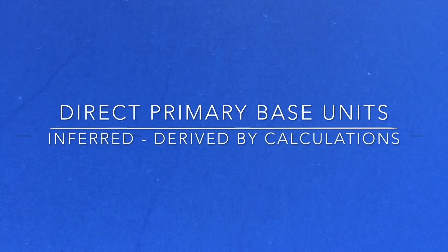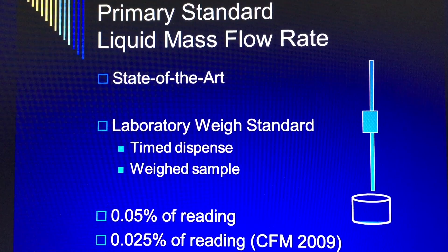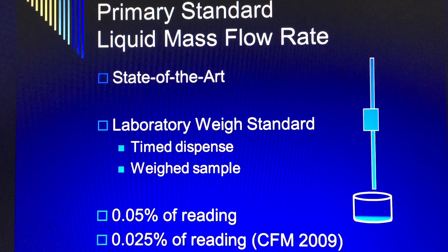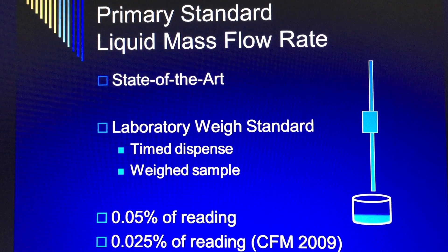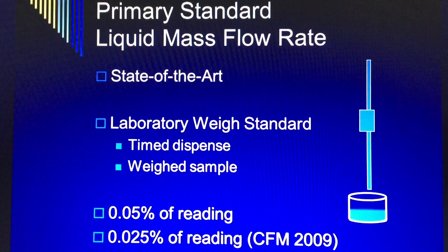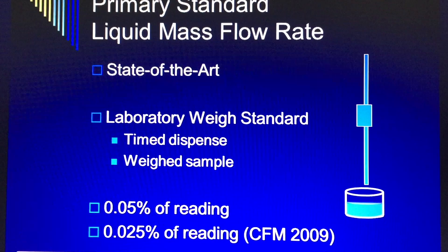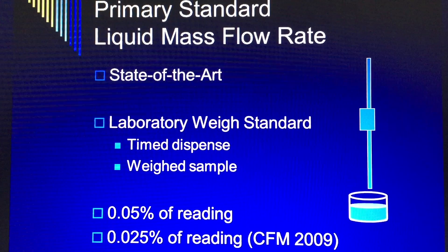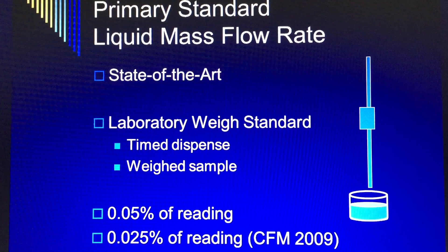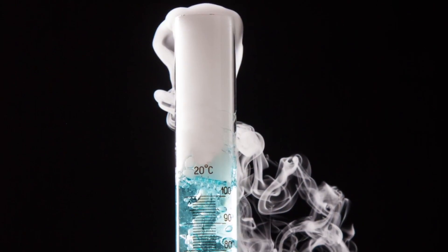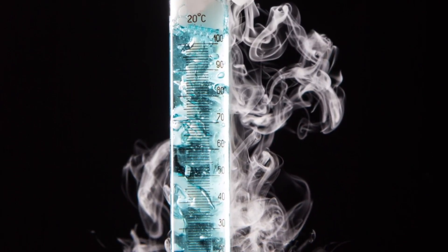Flow rate can be measured directly using primary base units or inferred, derived by calculations. A timed dispense, also known as the bucket and stopwatch approach, is a primary unit standard for flow rate. When the collected sample is weighed, it is a mass flow standard. When the sample is collected into a graduated volume container, it is a volume flow rate standard.